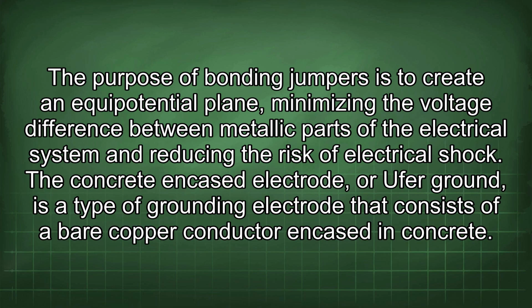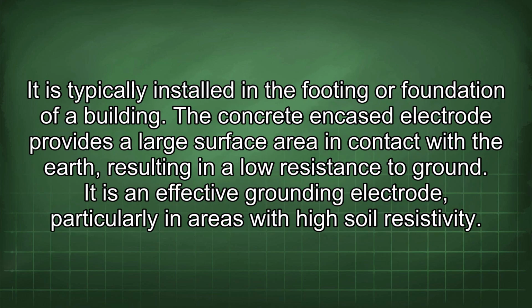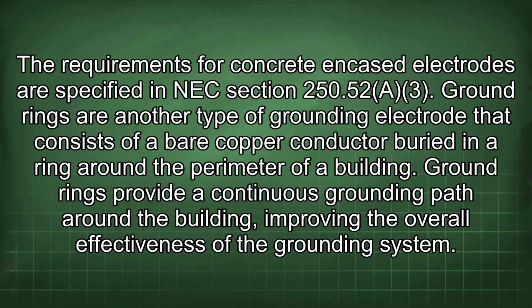The concrete encased electrode, or Ufer ground, is a type of grounding electrode that consists of a bare copper conductor encased in concrete. It is typically installed in the footing or foundation of a building. The concrete encased electrode provides a large surface area in contact with the earth, resulting in a low resistance to ground. It is an effective grounding electrode, particularly in areas with high soil resistivity. The requirements for concrete encased electrodes are specified in NEC Section 250.52(A)(3).